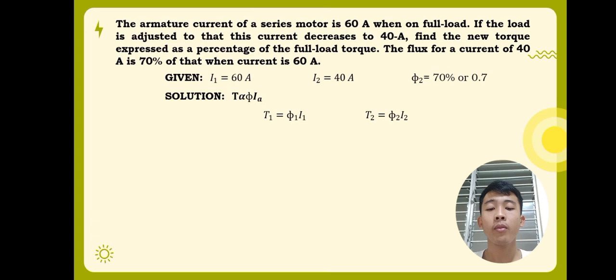Then, we can now have the formula T1 over T2 is equal to flux 1 times armature current 1, all over flux 2 times the armature current 2. After obtaining this formula, we can now substitute the given values, which will yield T1 over T2 is equal to 60 over 40 times 0.7. Calculating this, we can have the value T1 over T2 is equal to 2.1428.